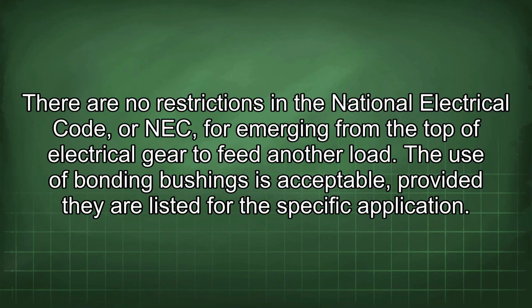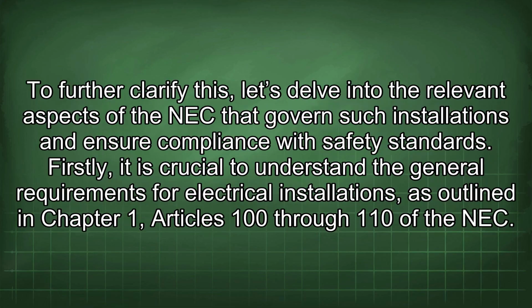There are no restrictions in the National Electrical Code, or NEC, for emerging from the top of electrical gear to feed another load. The use of bonding bushings is acceptable, provided they are listed for the specific application.